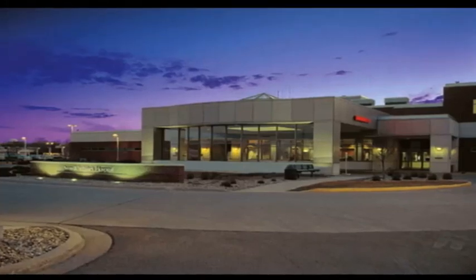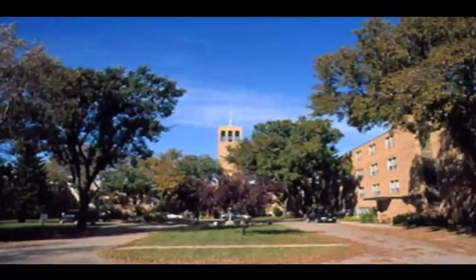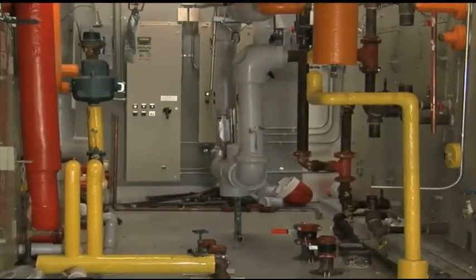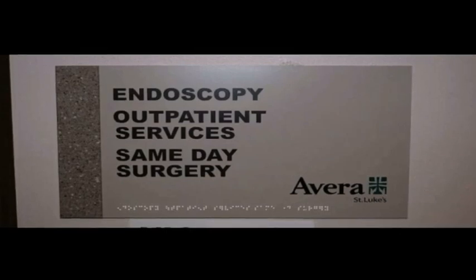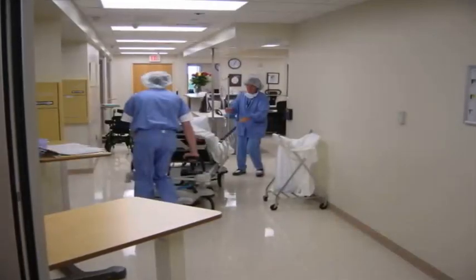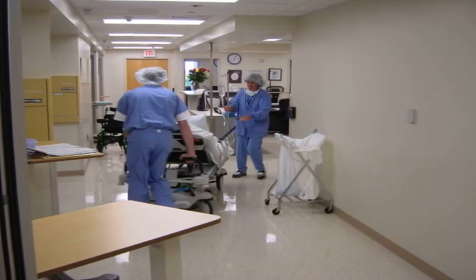For over 100 years, Avera St. Luke's Hospital has served the community of Aberdeen in eastern South Dakota. The east addition of the hospital, which was built in 1991, is served by air handlers in a central mechanical room. One of those air handlers serves the dialysis, endoscopy, outpatient services, and same-day surgery departments of the hospital. In summer months, the areas served by this air handler experienced excessive humidity.